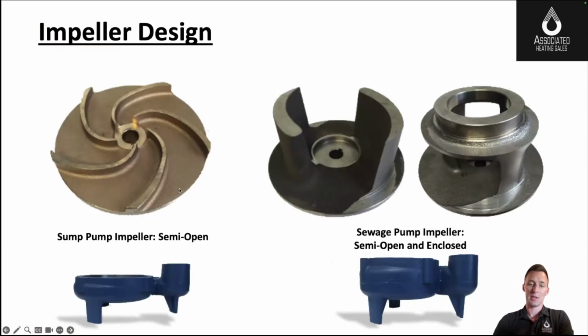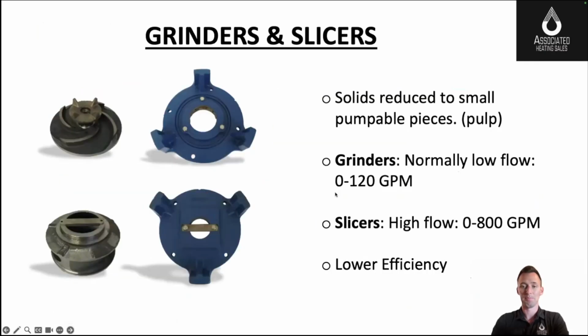The big difference is the case and the impeller. On the left, you see the groundwater pump where the impeller is in tight tolerance to the case, and you're typically only moving 1/2 inch solids through this pump. So this is groundwater. On the right, you have a sewage pump where the impeller can pass 2-inch solids through it. That's how we define our sewage pumps. They can pass 2-inch solid spheres through the pump, and that's going to make it a sewage pump.